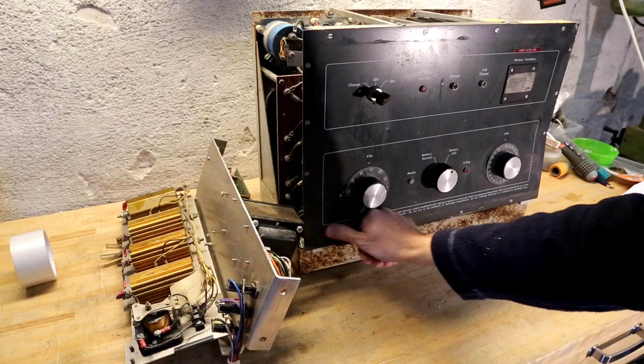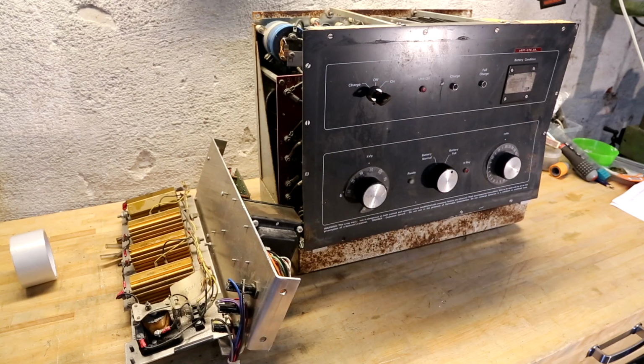And then there's a huge warning down here at the bottom. Warning, this X-ray unit is dangerous to both patient and operator unless established safe exposure factors are observed. Read accompanying instructions. Sold to be used only by or on the prescription of a licensed physician. Danger, explosion hazard. Do not use in the presence of flammable anesthetics. Do not recharge batteries in a confined or unvented area. So yeah, this is completely something you would want in a hospital.